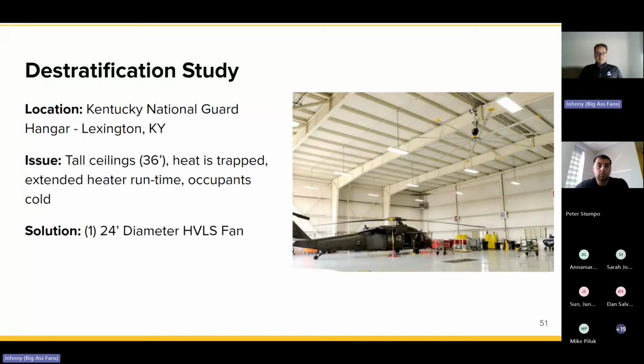We took a hangar project that was, again, near our head office, and we did a study with them. They had 36-foot ceilings. We ended up installing one 24-foot diameter fan, so a massive ceiling fan. We wanted to measure the temperature in the space, look at their heater run times and ultimately their gas usage, and see how we can impact that.